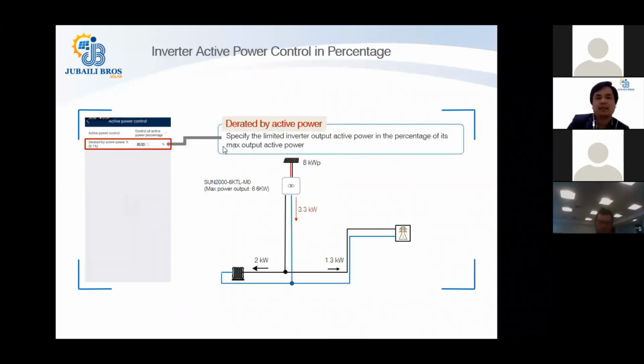And you can limit now the output power of the inverter based on the percentage as well, as I said. Let's take this simple case where we have an inverter of 6 kilowatt, the 6 KTL-M0, which is a three-phase Huawei inverter. And if you are connecting 8 kilowatt peak, the generation can go more than 6 kilowatt at some point of time if the weather conditions are very good. So with the maximum power output of this inverter, which is 6.6 kilowatt, all Huawei inverters have a generation capacity of 10% extra than the rated power. So a 6 kilowatt can provide you up to 6.6 kilowatt up till a certain temperature.